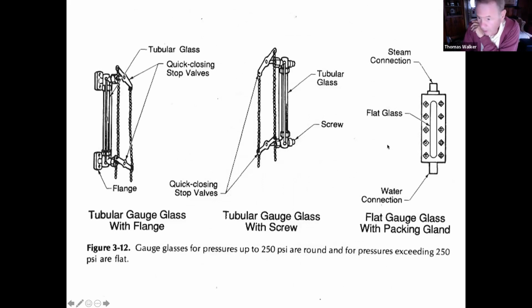They do have a question on the state exam. When is a flat gauge glass used? That's generally reserved for pressures above 250 PSI. For pressures below that, we typically see tubular gauge glass.